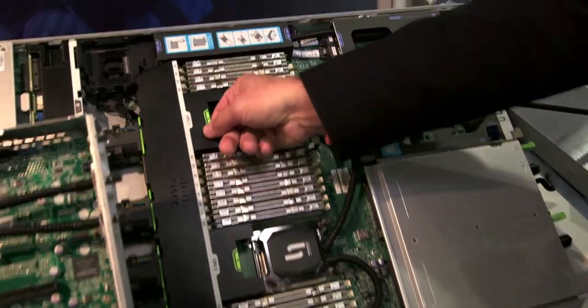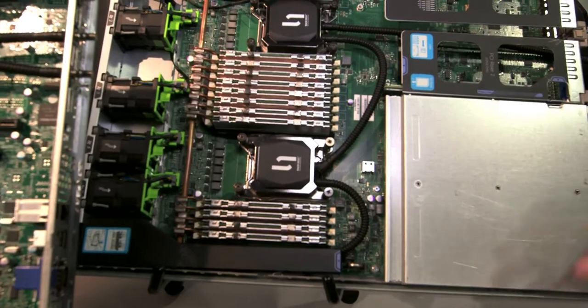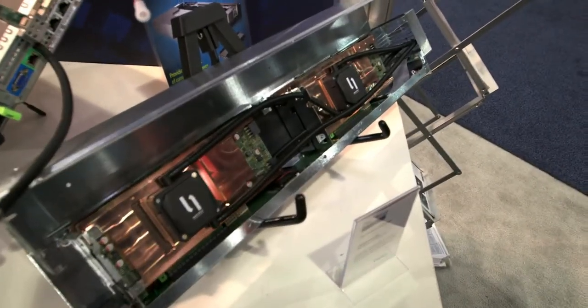So if I lift the cover up, you can actually see that we're using little heat pipe links to cool the memory, utilizing the liquid channel or the cold rail that goes down along beside the RAM. So you don't have to force air to cool the memory — you can do liquid cooling throughout the system. It was done as a special project, an option. For the most part, our customers are most interested in gathering heat from the hottest points in the system. We also have a nice example here of another customer, One Stop Systems — they are doing liquid-cooled Xeon Phi.